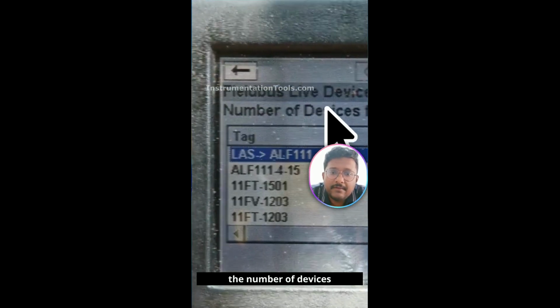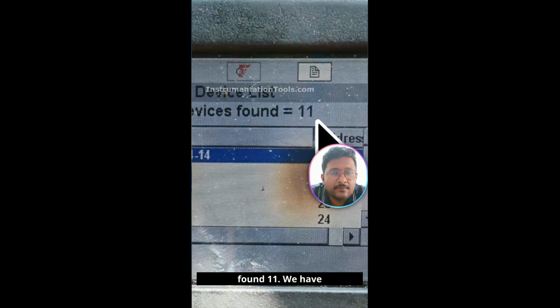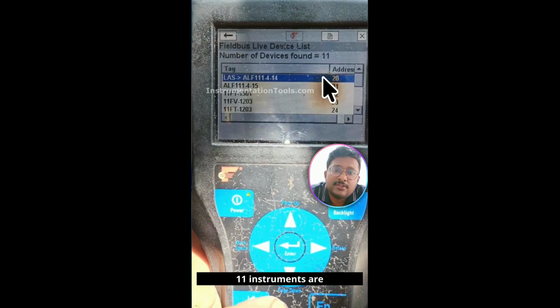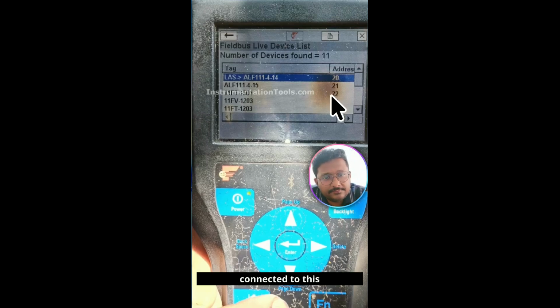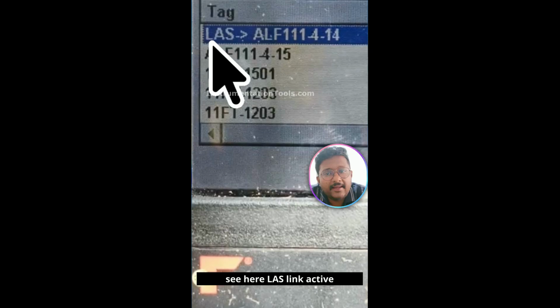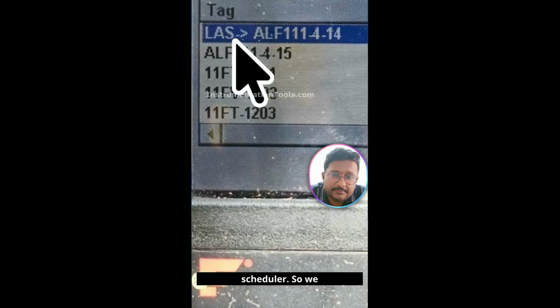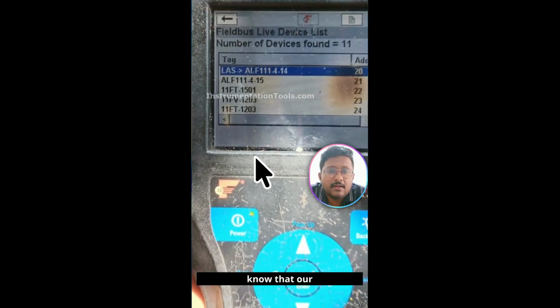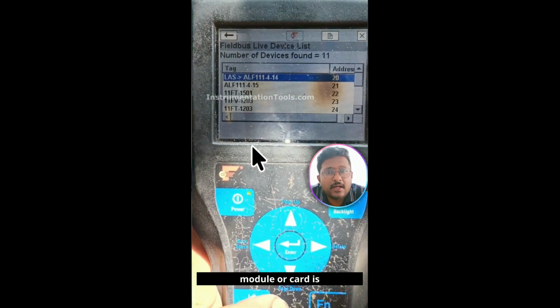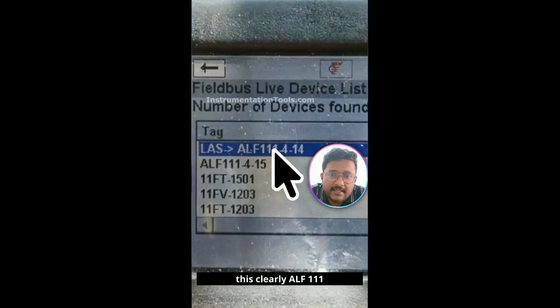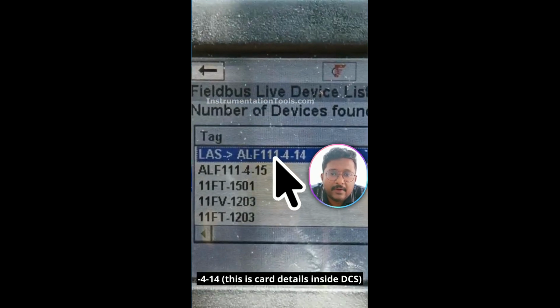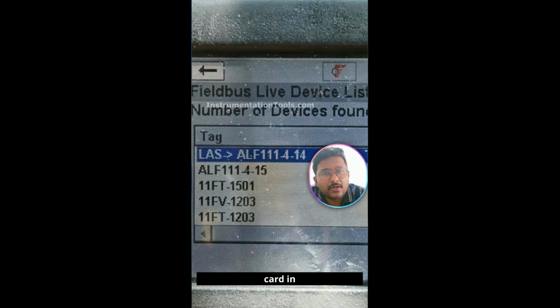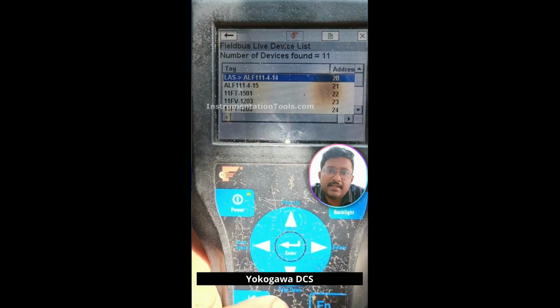You can see the number of devices found is 11. We have a total of 11 instruments connected to this junction box. You can see here LAS, link active scheduler. So we know that our foundation fieldbus module or card is called the link active scheduler. You can see this clearly, ALF111. ALF111 is the foundation fieldbus IO card in Yokogawa DCS systems.